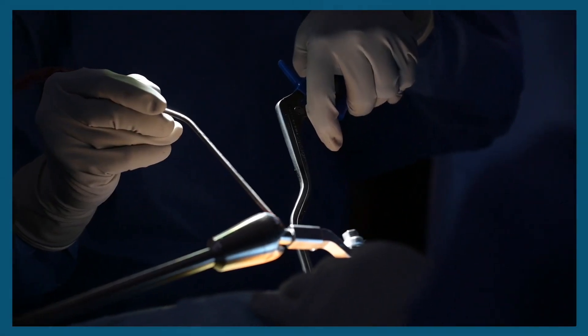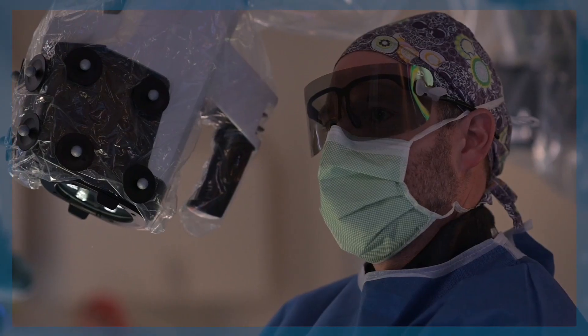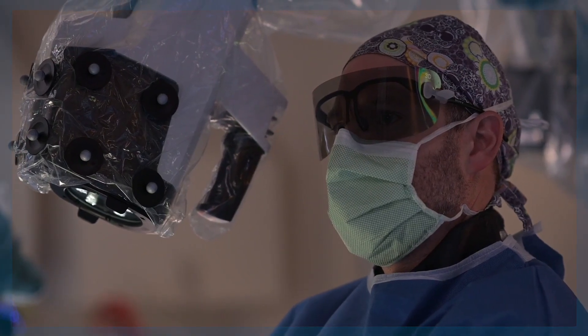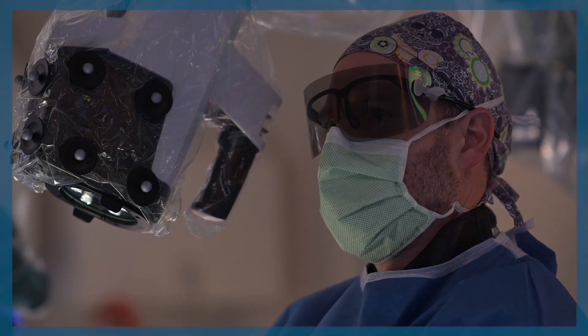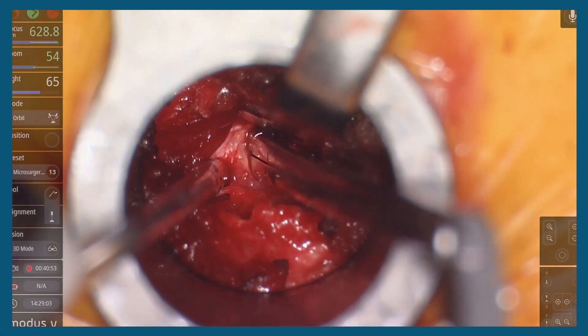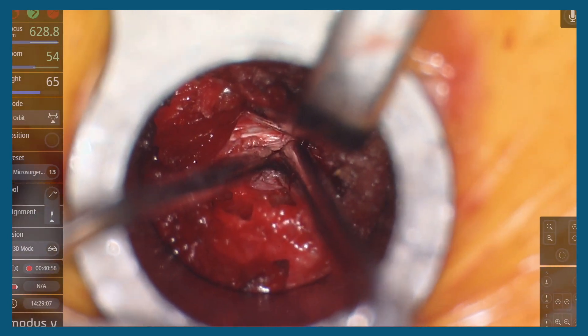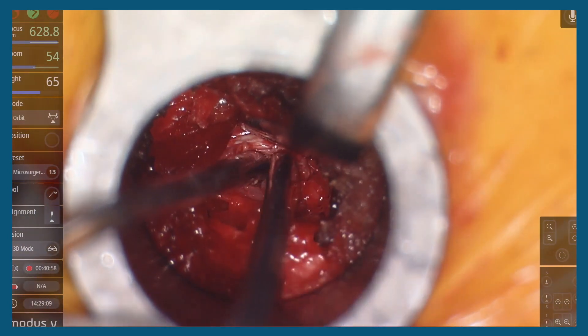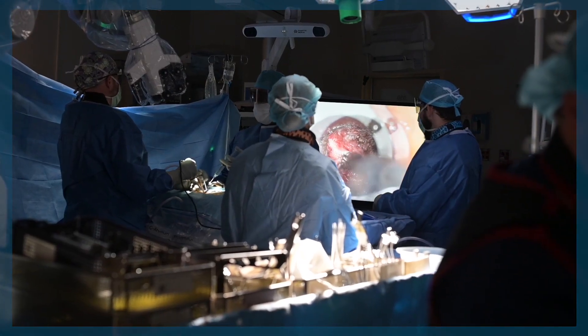There are ways to store settings and go back to that initial position later on in the surgery, so you can flip back to that other view without having to remember where that was or having to maneuver a big microscope around in the field. I think it just overall reduces a lot of frustrations, and if you're able to provide a procedure that's easier, more comfortable, and fluid for your patient, then the patients are going to have less time under general anesthesia and an easier time getting through their surgery.